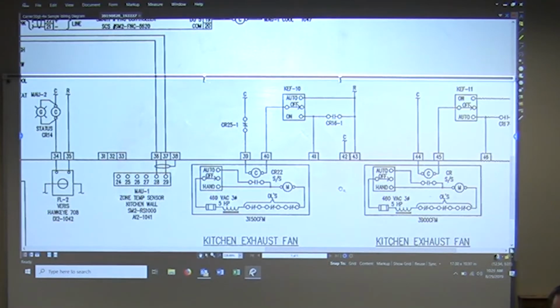Shuts it down. Okay, so more than likely this is what? Interlock safety, something like that, right? We don't see it on this page. We'd have to go to page 2. But if that opens, it's going to basically remove the flow of electricity through that coil. How should we have probably wired this so that it was more correct or better practices? You don't want to fail things on, well, I guess some things need to fail on, but this probably needs to fail off, rather than on.